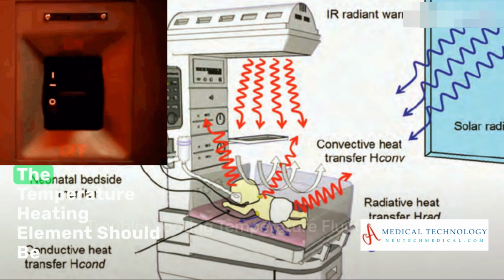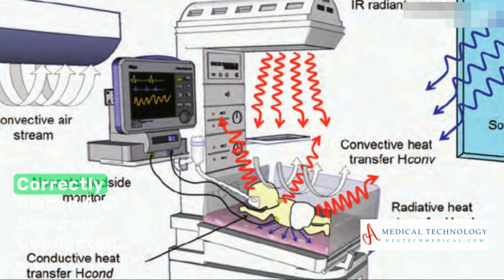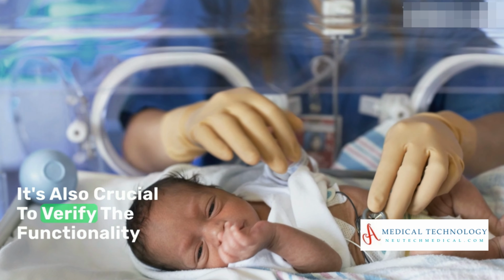Firstly, consider temperature fluctuations. The temperature heating element should be correctly placed and securely connected. It's also crucial to verify the functionality of the skin and air sensor. If necessary, calibrate the skin and air probe along with the temperature control system.